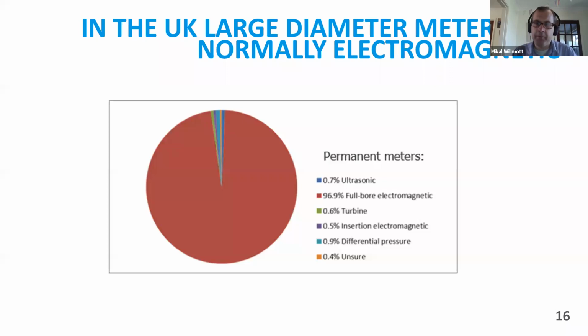WRC did a survey of maybe half a dozen water companies about 5 years ago to look at what type of meters we use for large diameter metering and system input volume metering especially. And in the UK, you'll see that full bore electromagnetic meters came out on top by quite a distance. Almost 90%, 97% of meters in the UK, SIV meters, were electromagnetic meters.